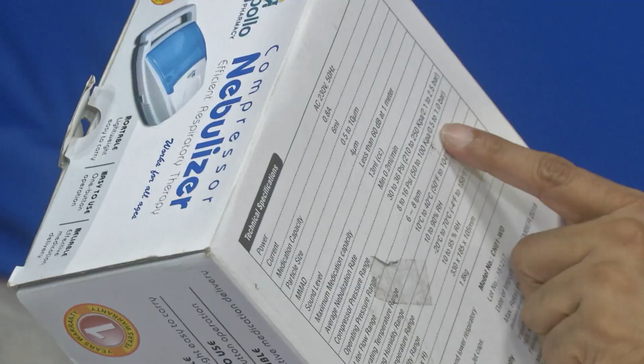Let us do a small demonstration. What is of interest is to monitor the pressure built by a simple nebulizer. This is a nebulizer which you can buy for about 2000 rupees or so. If you look at the data sheet here, it can generate an operating pressure range of about 0.5 to 1 bar. The compressor can work up to 2.1 to 2.5 bar, but the operating pressure range is 0.5 to 1 bar. Its equivalent in kilopascals is also mentioned on the left side, but that is not the focus of this discussion.